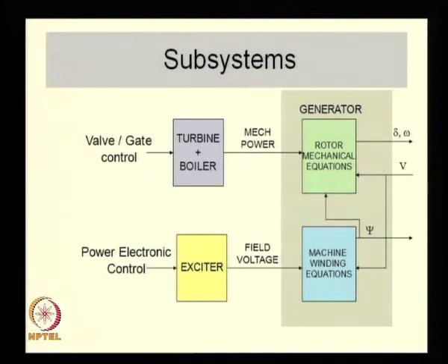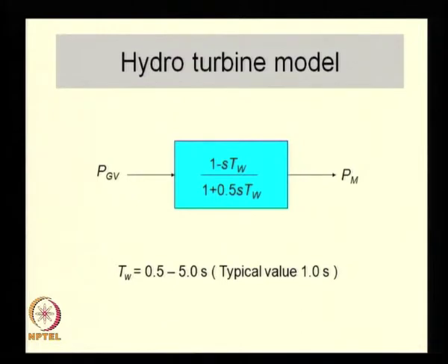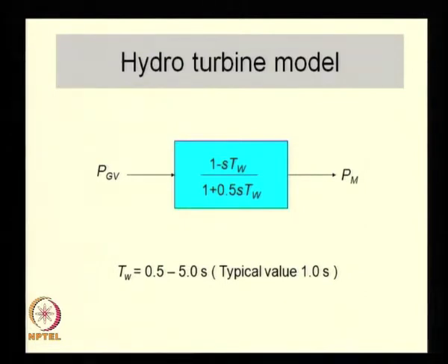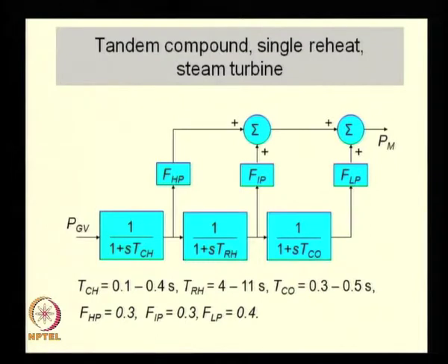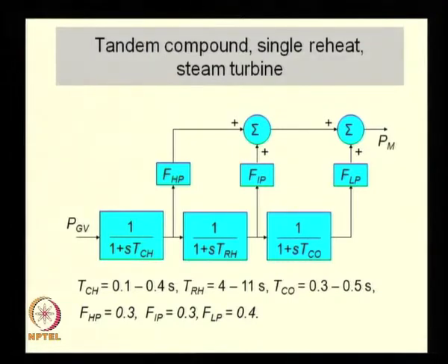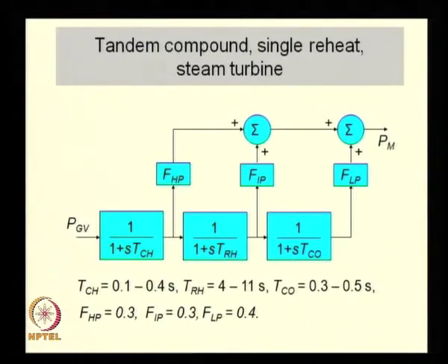In the previous class, we saw models of these turbine systems. One was of a hydro turbine — a very simplified model, suitable only for simple studies. One important point brought out last time was that a hydro turbine model is of non-minimum phase type; it has a zero on the right-hand side of the S-plane. We also saw a steam turbine model — a tandem compound single reheat steam turbine — where each turbine stage (FHP, FIP, FLP) contributes to the mechanical power: the high pressure, intermediate pressure, and low pressure turbines.